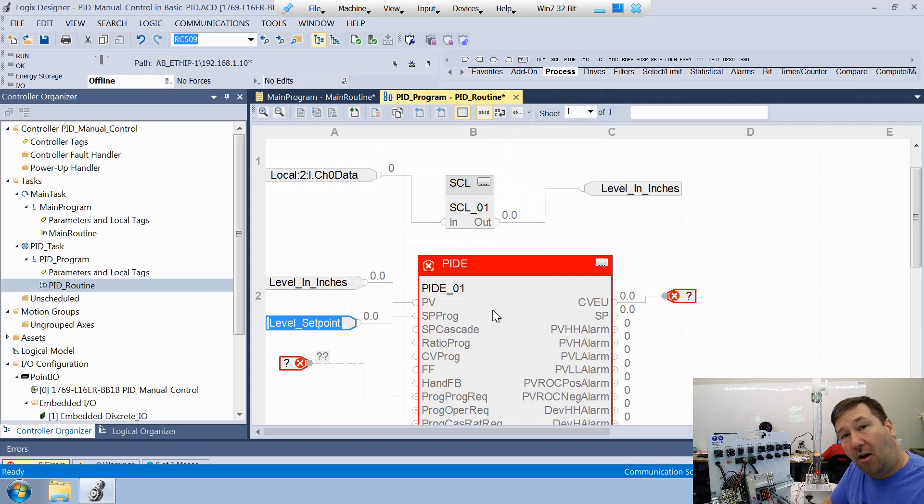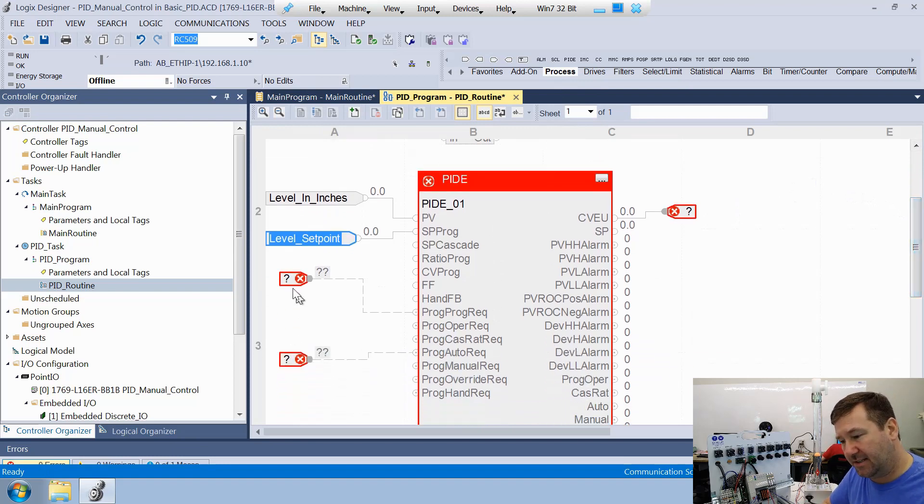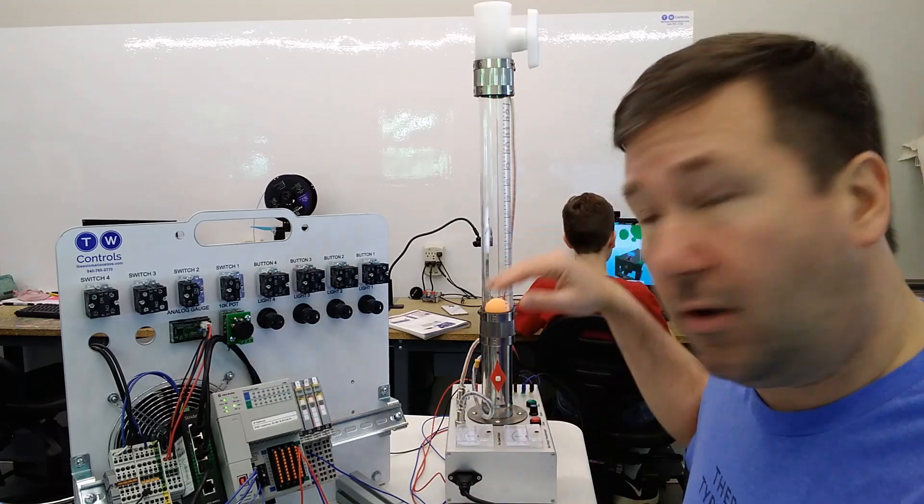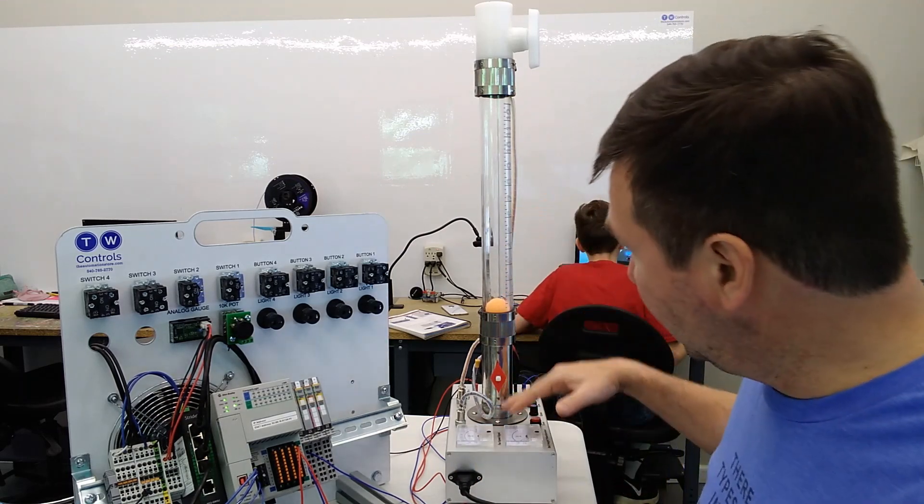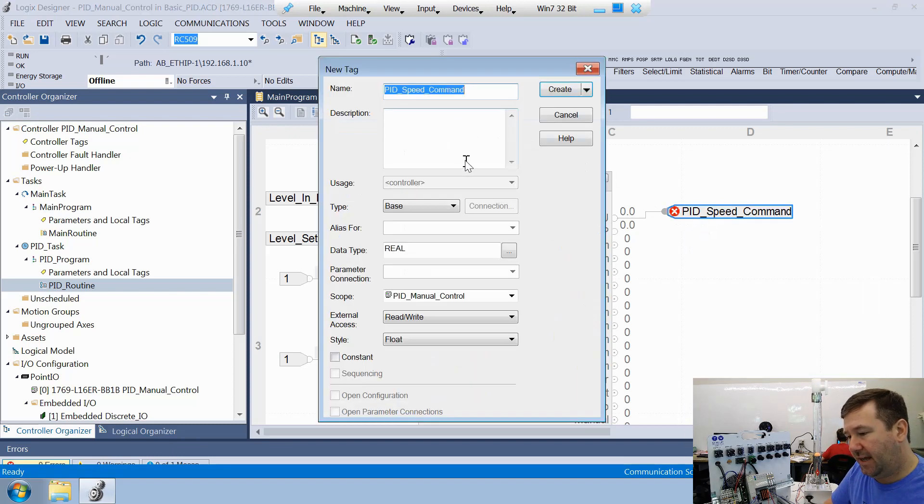And then we'll create a new one and it'll be a real. And then we don't always have to actually use tags in these. That's one reason I'm bringing these down for now. We're going to actually use these to do some things in later videos. But for now, we're just going to put a one on our prog prog request and on our prog auto request. And then we have our CVEU, which is our control variable or what we're going to try to use to force that level where we want it. So that's going to be our fan speed here. And we're going to use a tag for this. We're going to call it PID speed command. And we'll create a new variable for that. It'll be a real.